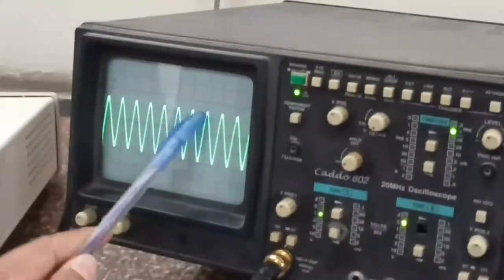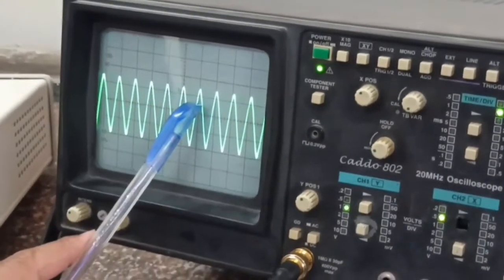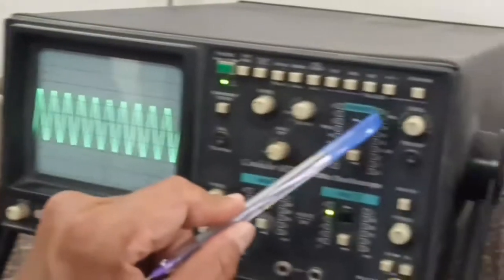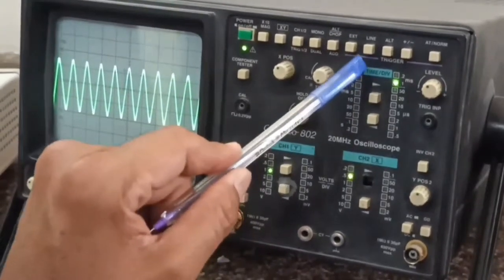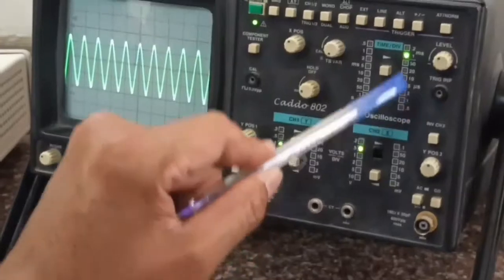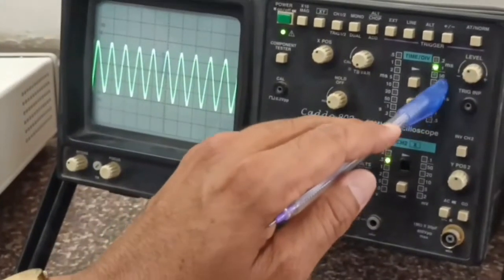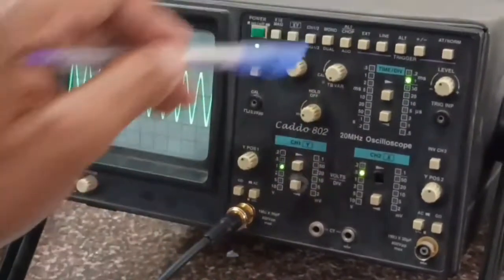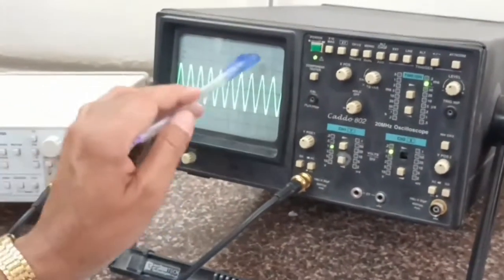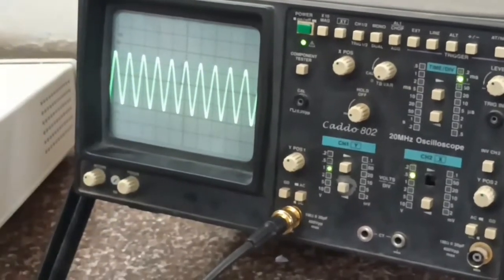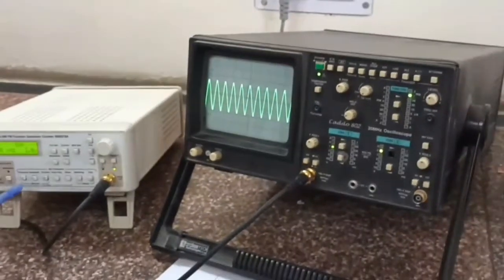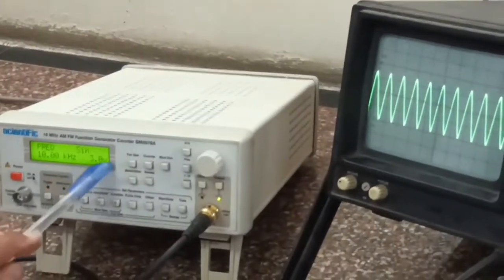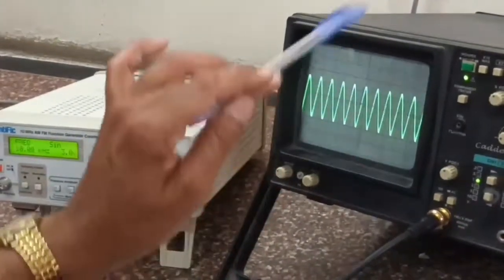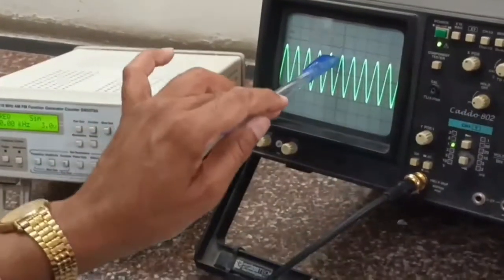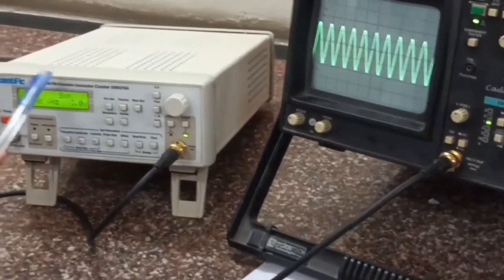So whenever you are calculating the frequency, the horizontal length may decrease or increase. It totally depends on what time base you have. The time base is nothing but time per division. In the first case we saw 50 microsecond, and in the second case we considered 0.1 millisecond. After all, the result is the same, but you see the variation on the CRO. So this is the way to calculate the frequency using CRO. You can change the frequency from this point and then calculate again. In the same way, you change the voltage, see the vertical length, use your voltage sensitivity, and calculate. So this is the way to calculate voltage and frequency using CRO.